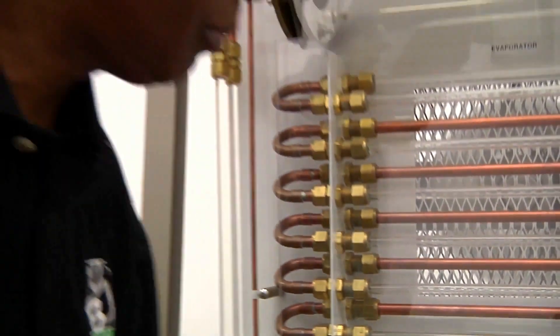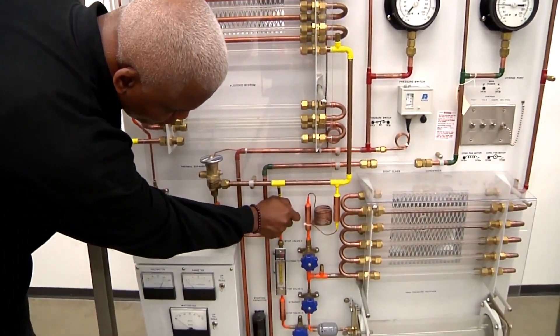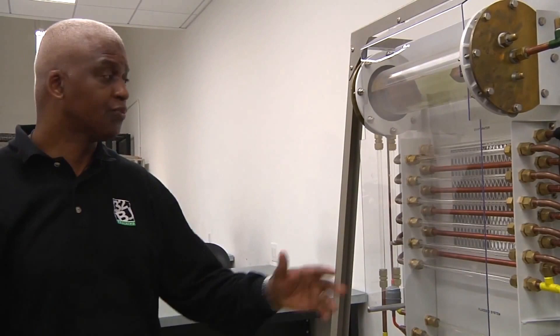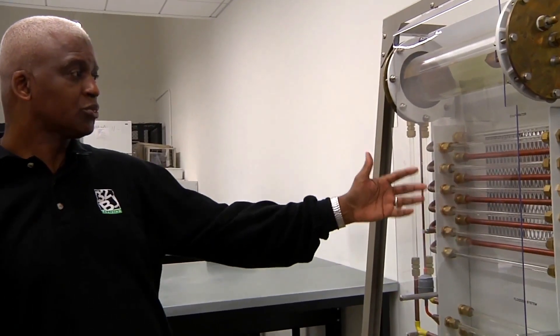Next we want to start our compressor. After we turn on our compressor, we come over to our hand operated expansion device because we want to establish a flow rate of 45 milliliters. So let's open this and get that flow rate established. We'll let that sit for about three to four minutes so we can establish good refrigerant flow throughout the entire system. If you look closely, you can see the refrigerant flowing through the system — it's actually boiling in the evaporator and condensing in our condenser, and you can see it trickle down into our receiver.